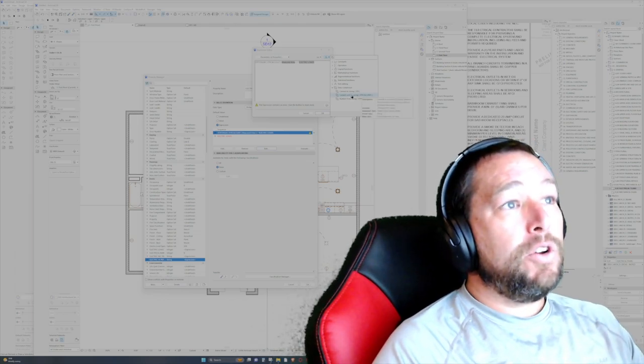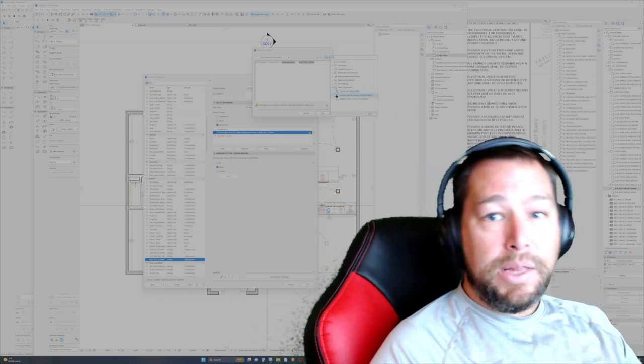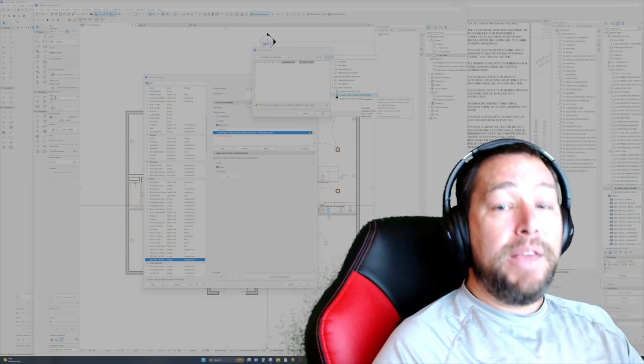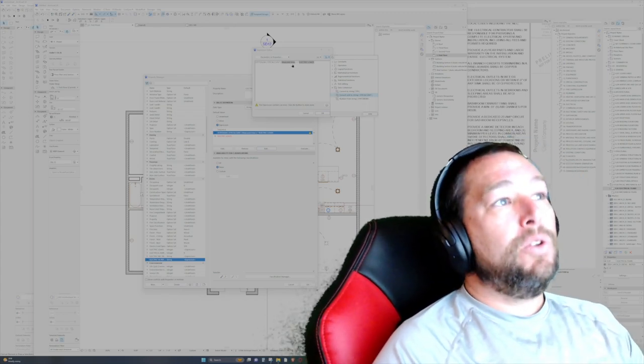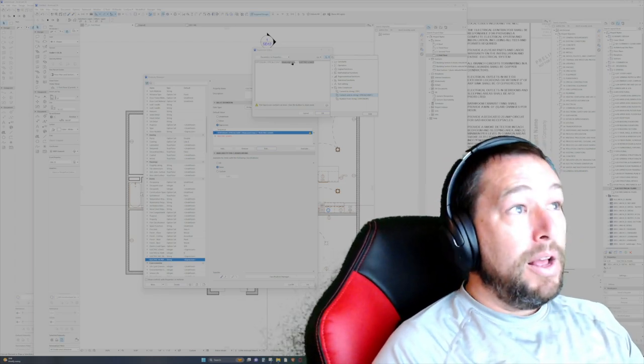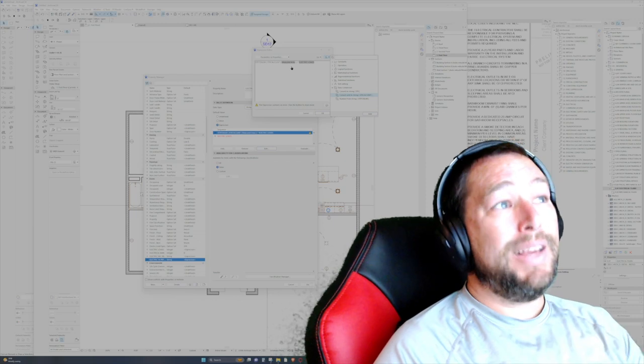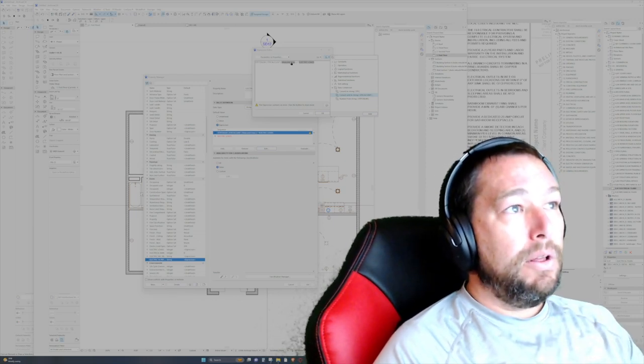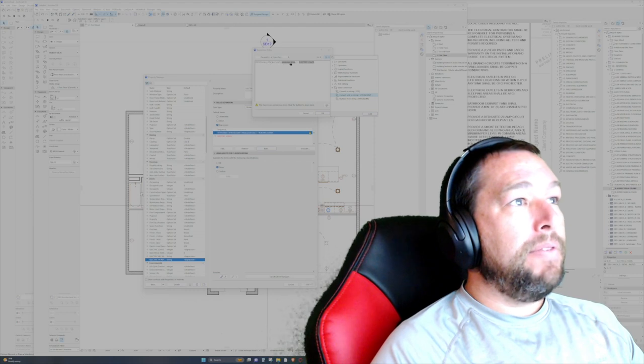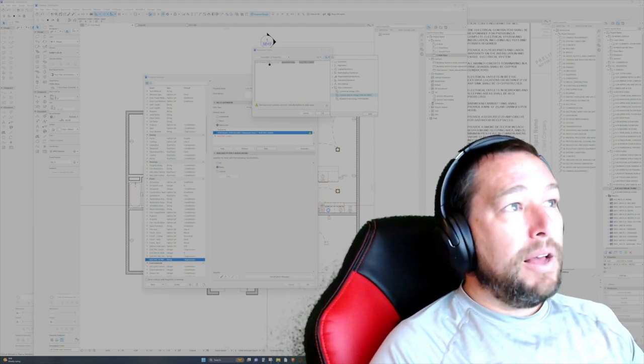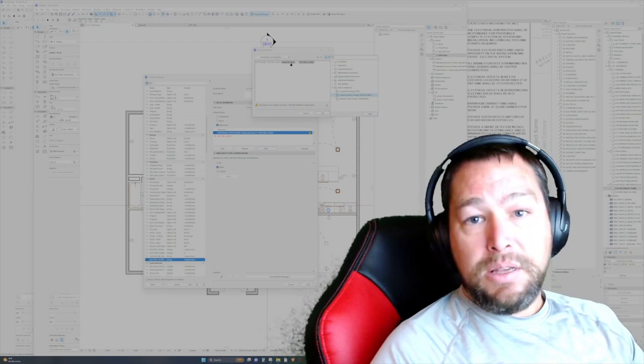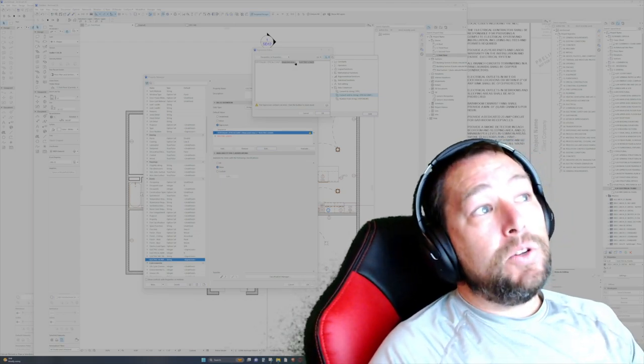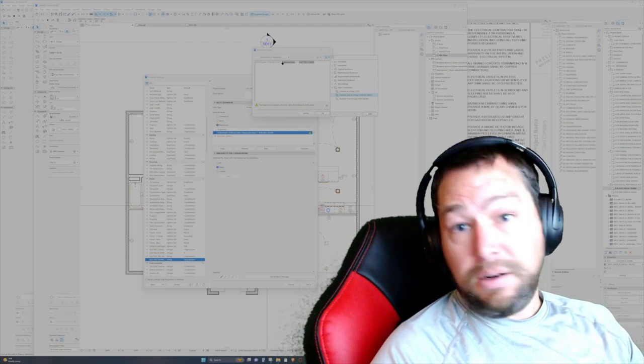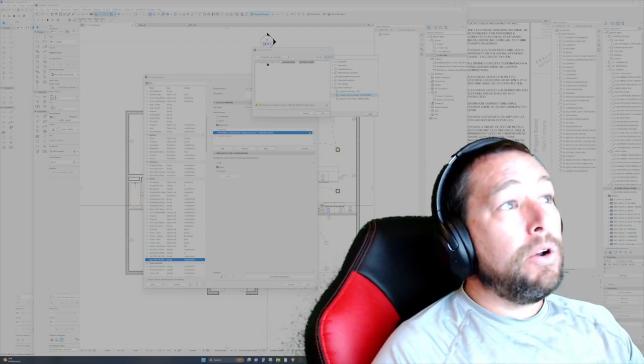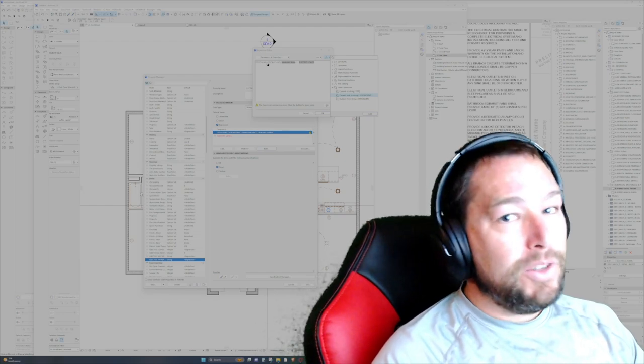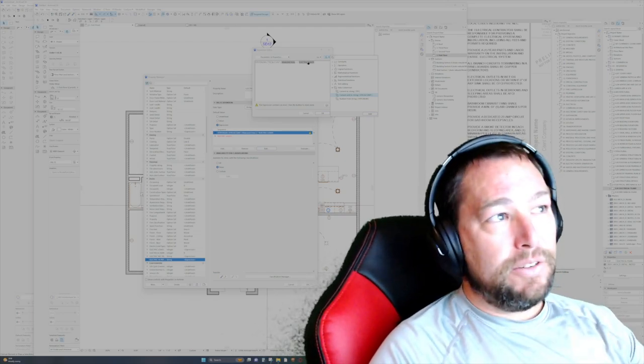So that's convert unit to string. The reason why is we need to eliminate the square foot or area unit from the measured area of the zone and convert it into an integer so that it can play nice with the other numbers. So this string calc unit takes the zone square footage and converts it into a string, basically numbers and letters, and then this string to number converts the numbers of the string and converts it to an integer.